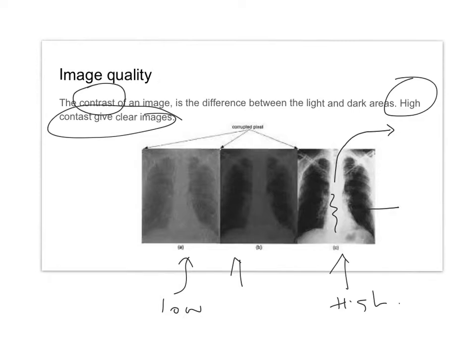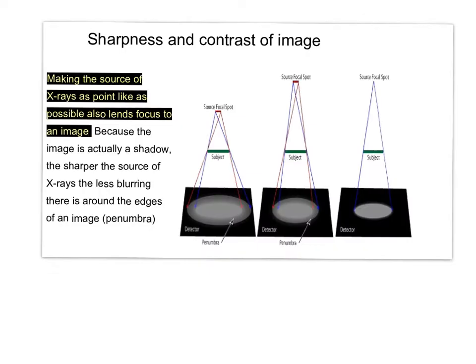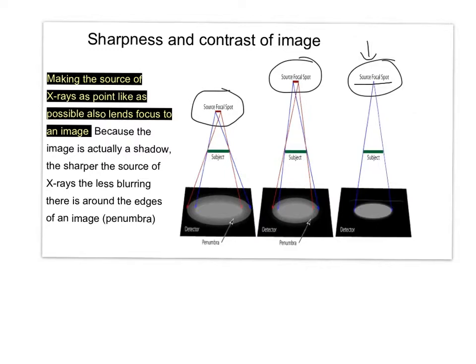Now we're going to look at how to increase sharpness. Increasing sharpness is all about the source of the x-ray. As you can see from these images, the smaller the point of emission of the x-rays — the source focal spot — the greater the sharpness will be. Because what we're trying to avoid is this area of shadow. These shadows are caused when you have a focal spot which is wide.